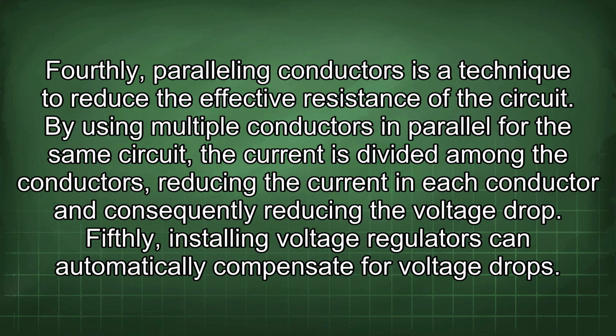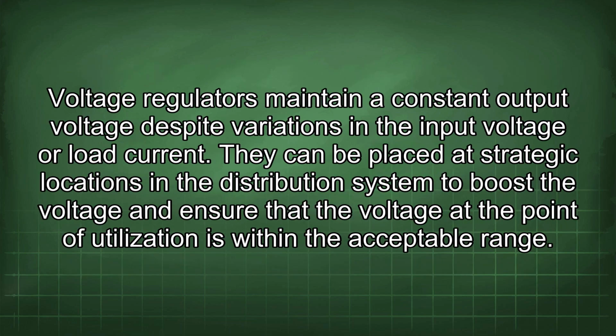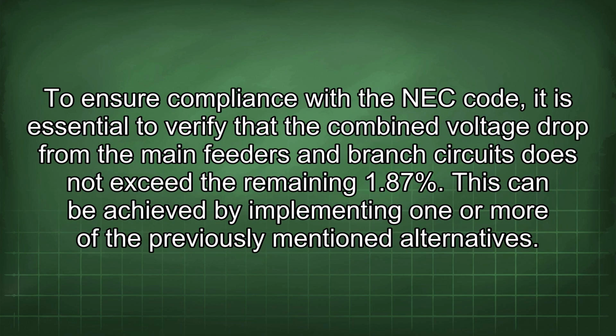Fifthly, installing voltage regulators can automatically compensate for voltage drop. Voltage regulators maintain a constant output voltage despite variations in the input voltage or load current. They can be placed at strategic locations in a distribution system to boost the voltage and ensure that the voltage at the point of utilization is within the acceptable range. To ensure compliance with the NEC code, it is essential to verify that the combined voltage drop from the main feeders and branch circuits does not exceed the remaining 1.87%. This can be achieved by implementing one or more of the previously mentioned alternatives.